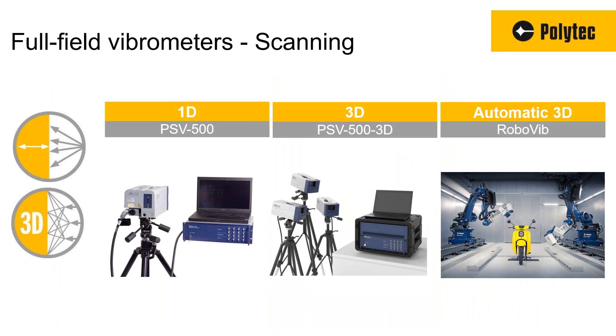For full-field sequential scanning systems: here's what a 1D scanning vibrometer looks like. Add a couple more scan heads and you have a 3D scanning vibrometer, which comes with a computer or laptop. If we take this 3D scanning vibrometer and mount it on a software-controlled robot, we can scan large or complex-shaped structures with a click of a button — teach the robot where to go and it takes over the measurement. This covers full-field sequential scanning-type systems.